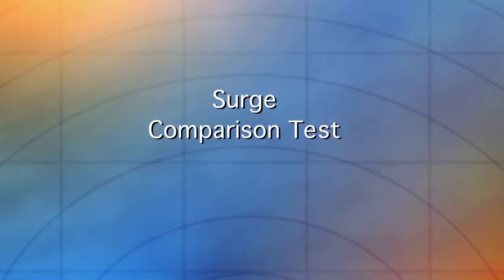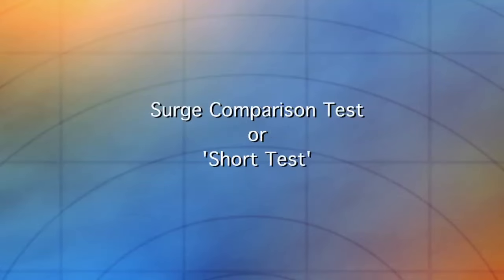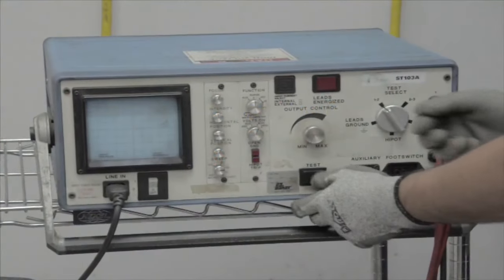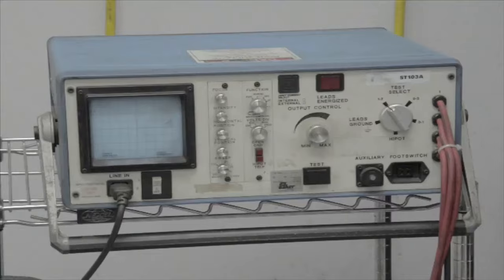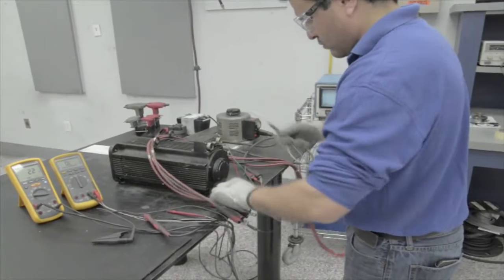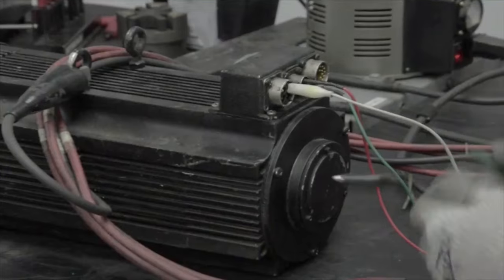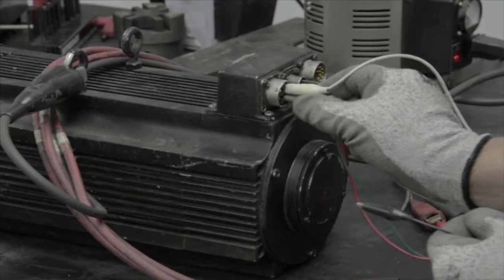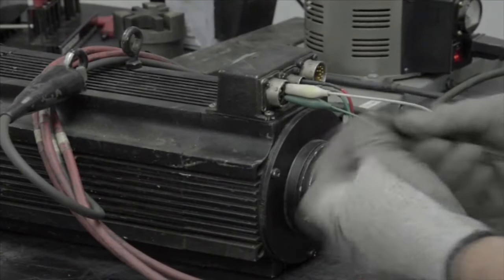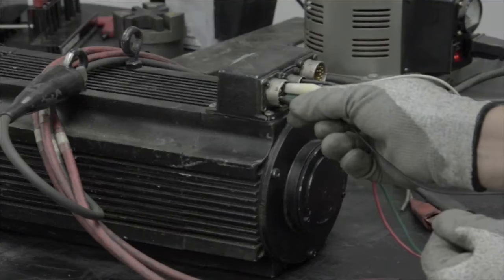The next step is for the technician to perform a surge comparison test or short test. He is using a surge tester to verify whether or not the stator will need a rewind, first connecting the ground to the motor and then connecting three leads to each phase of the motor. The surge test checks the strength of insulation and for any shorts, turn to turn, layer to layer, or phase to phase.